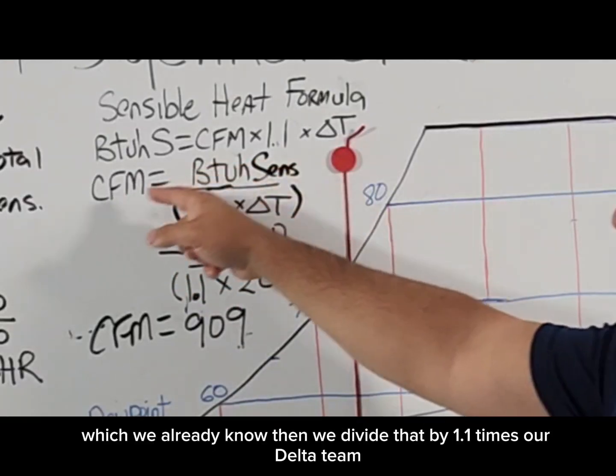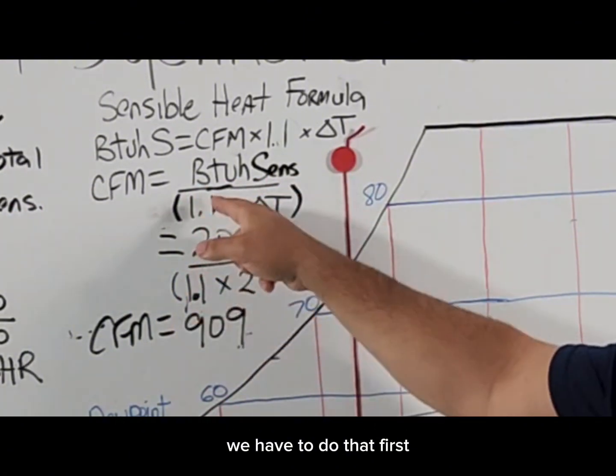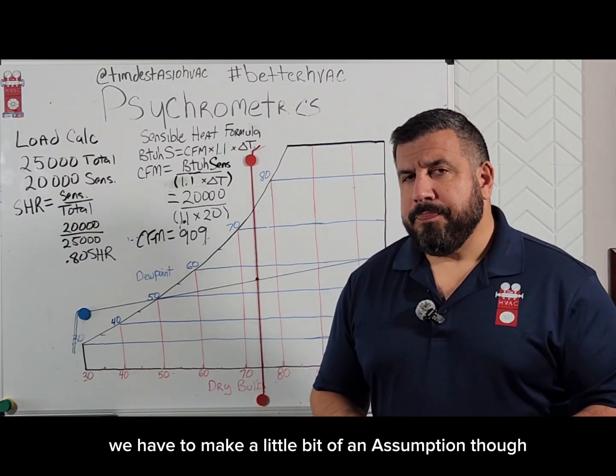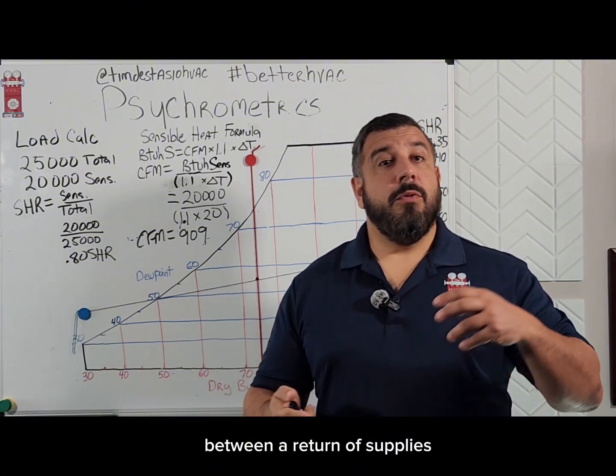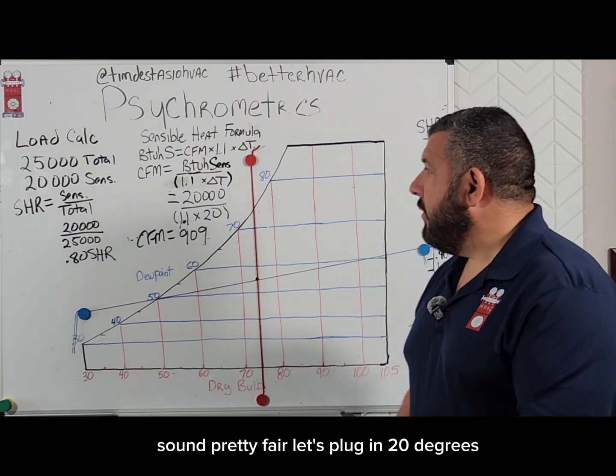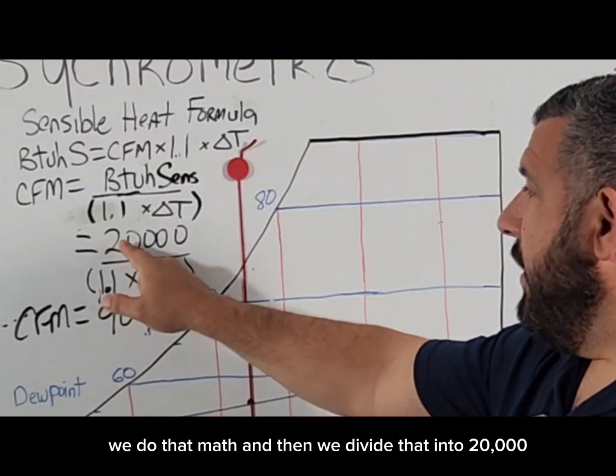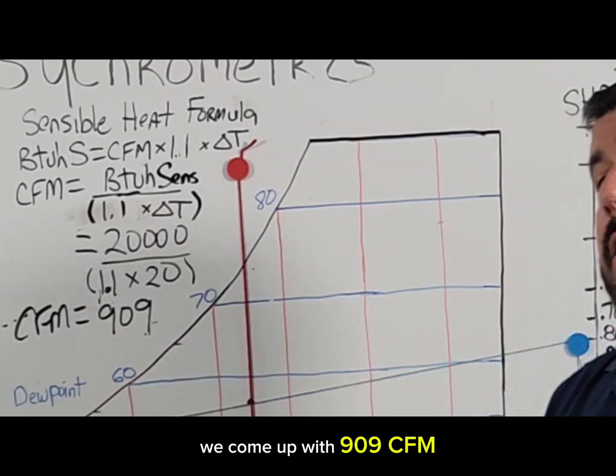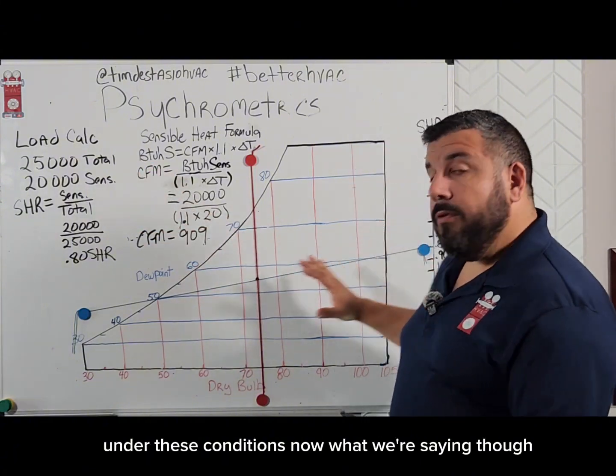Here's what it looks like: CFM equals BTU sensible divided by (1.1 times delta T), and we calculate the denominator first. We need to assume a delta T — 20 degrees is a fair assumption for the temperature drop between return and supply. So we take 1.1 times 20, then divide that into 20,000 BTU sensible, and we come up with 909 CFMs — that is our target CFM for this load calculation under these conditions.